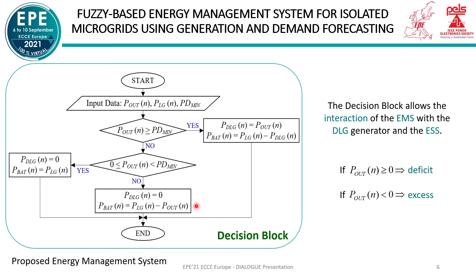The objective of the fuzzy logic controller is to modify the Pout profile to keep the battery state of charge oscillating as close as possible to 75% while permanently supplying the load. Also, the negative and positive variation range for both inputs and outputs provide better control to charge the battery and take power from the battery or diesel generator.